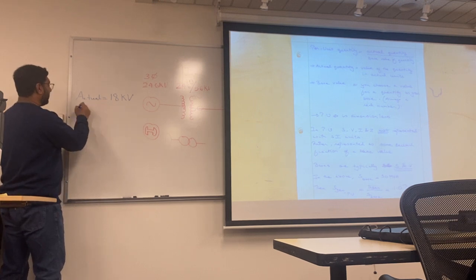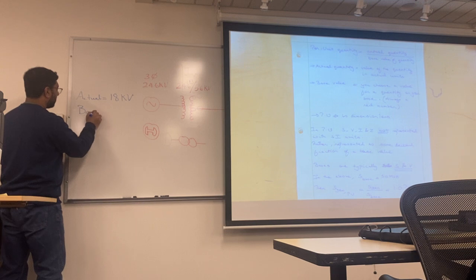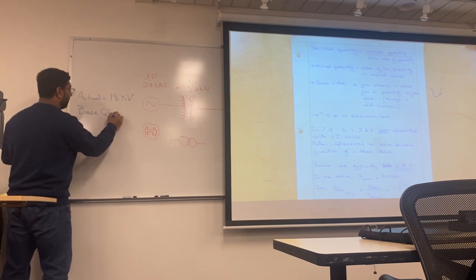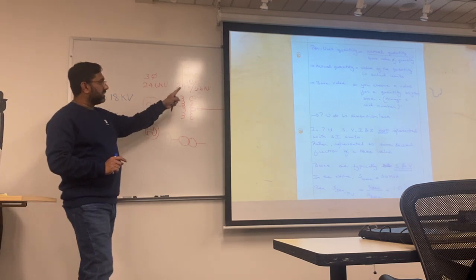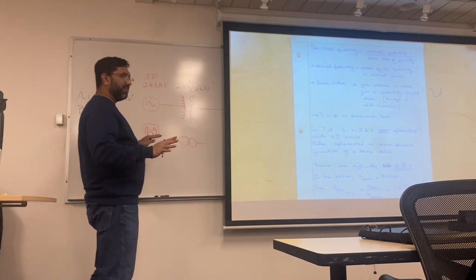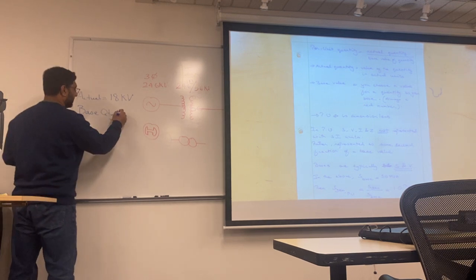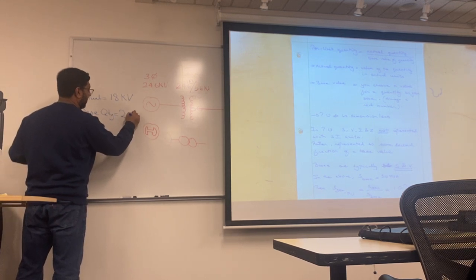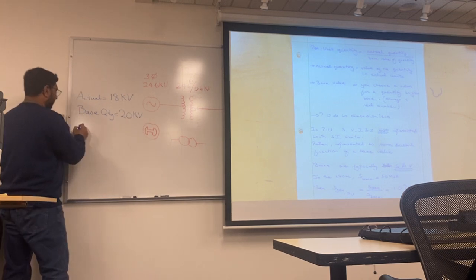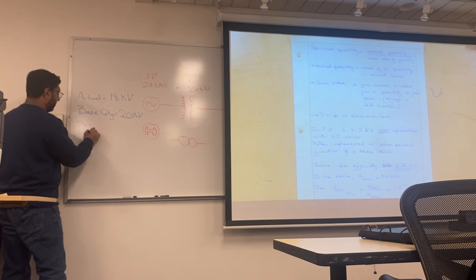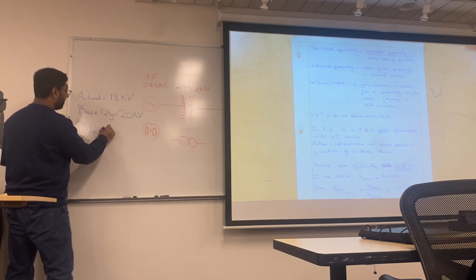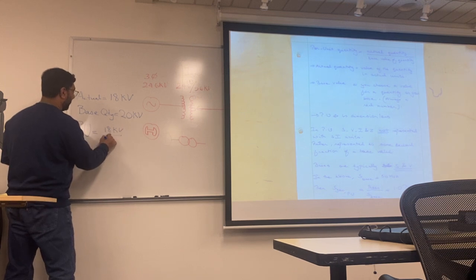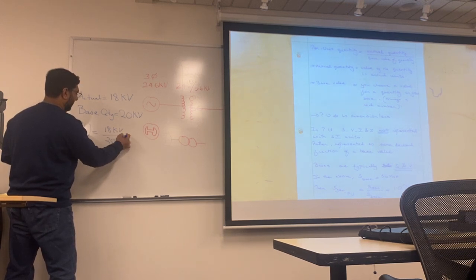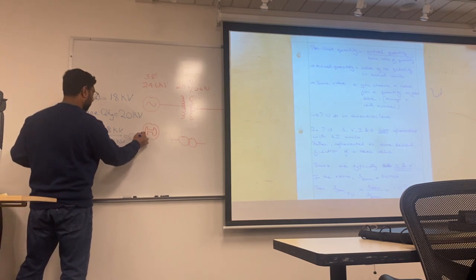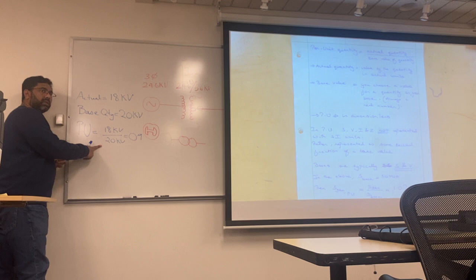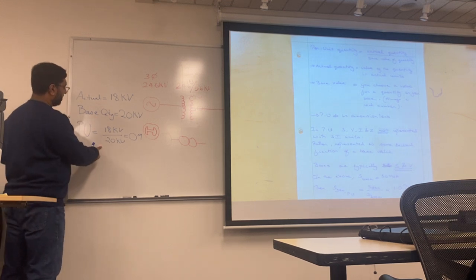The second quantity on the screen is a base quantity, this is a value that I choose. Looking at the system, I will choose a value that's going to be my base quantity. For example, I'm going to choose 20 kilovolts as my base. So my per unit, PU, is my actual, which is 18 kilovolts, divided by my base, which is 20. And I believe this is 0.9.